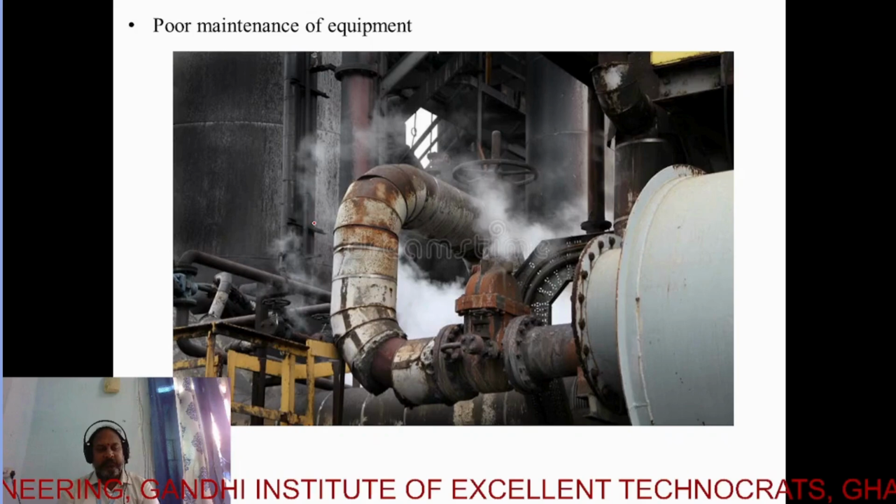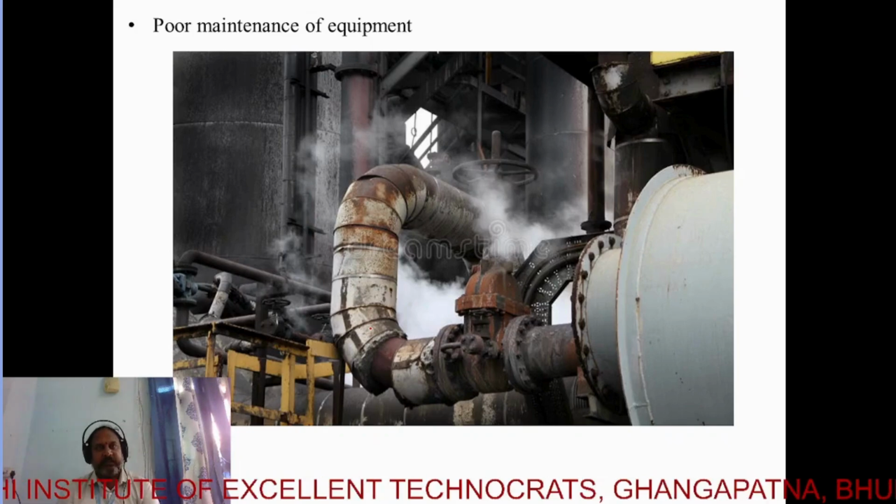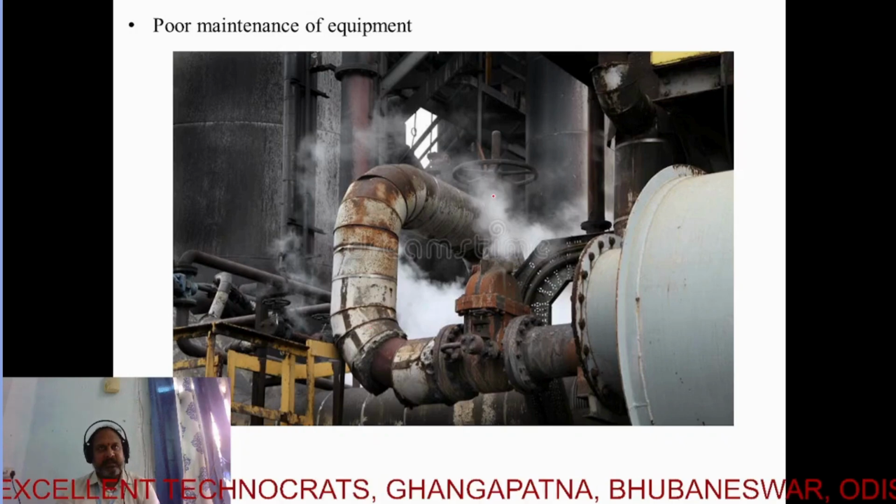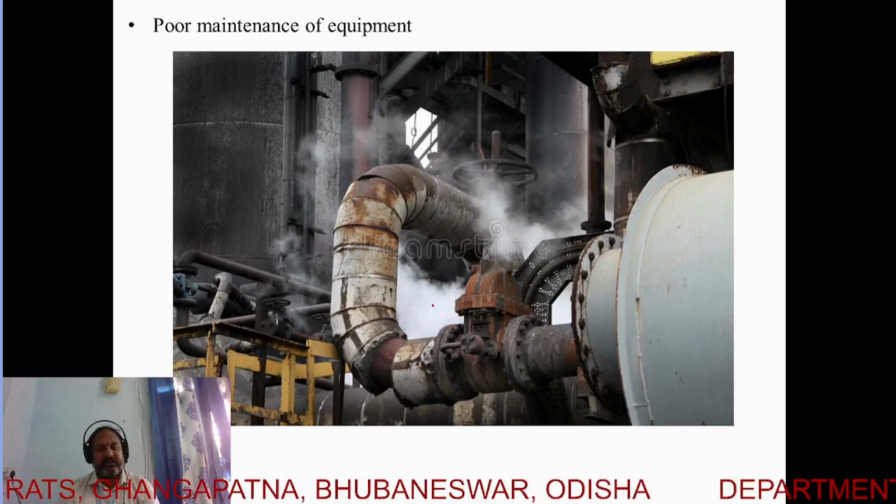Here the escaping steam suggests a problem. You can see the steam around here, which is suggesting either a gasket failure, a loose flange connection, or a corroded weld joint.